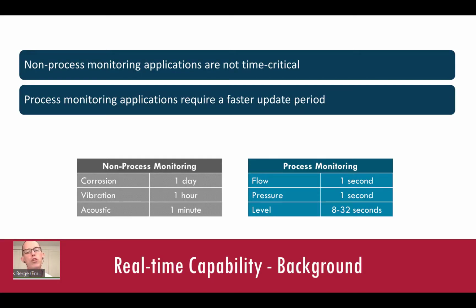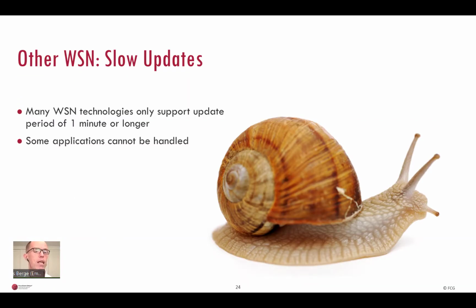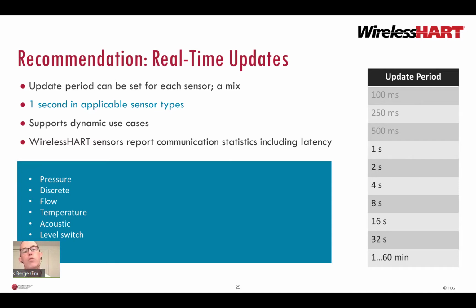Next requirement is real-time performance. WirelessHART sensors are mostly used in non-process applications, which are not time-critical, such as eliminating inspection and manual data collection. For these applications, an update period of 1 minute or 1 hour or even 1 day is enough. But in every plant, there are a few use cases that require faster update periods, such as 1 or a few seconds. Many other wireless sensor network technologies only support an update period of a minute or longer, meaning there are some applications they cannot handle. So you must wire those sensors instead, which is costlier and more disruptive. So be careful. WirelessHART solves this with real-time capability with update periods of 1 second in applicable sensor types. So if the use case really requires such a fast update period, it is possible with WirelessHART.